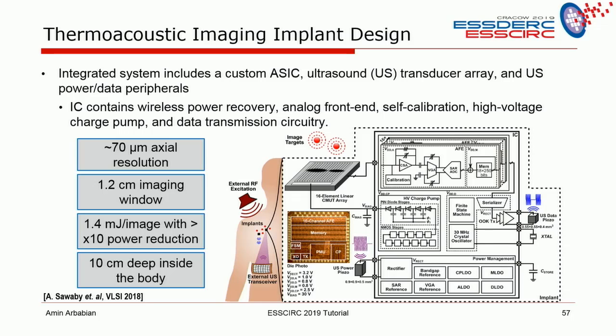It's integrated with a CMUT transducer that's different from one batch to the next. So what we do is, in every cycle of measurement, which is 1 or 2 frames per second, we inject calibration signals throughout the chain, from input of ultrasound through leakage and surface waves to the receiver prior to LNA, after the LNA, before the ADC, and so forth. So that's how we calibrate all components of the chip.